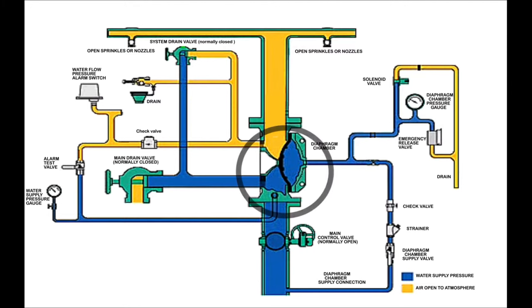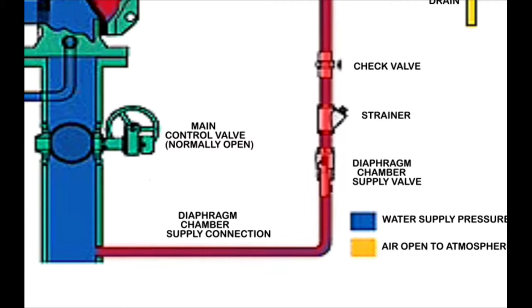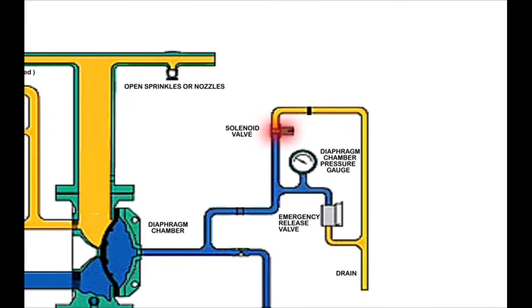This diagram shows the action of activating the solenoid valve in a deluge system, with the deluge valve in closed position. The blue color represents pressurized water, while the orange color represents atmospheric air. Here is the water supply pressure, and here is the priming water pressure, which is forcing the diaphragm in the forward position, balancing the water supply pressure and keeping the deluge valve closed. The priming loop branches from the water supply pressure and includes a manual valve, a strainer, a check valve, the solenoid valve operable from the control room push button, and the emergency release valve for manual activation.